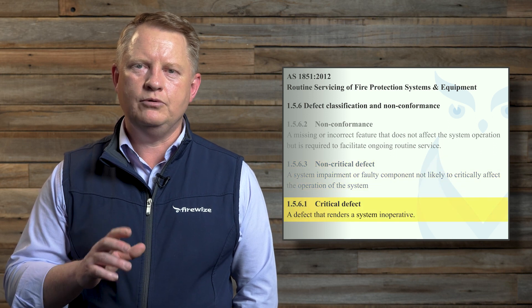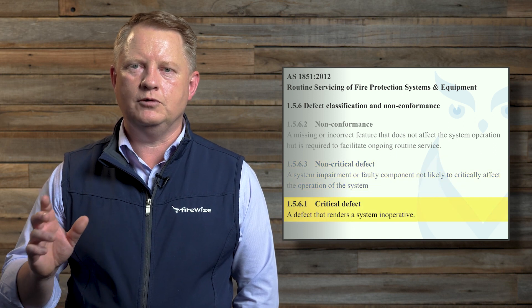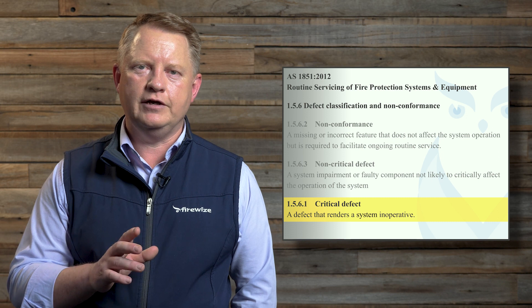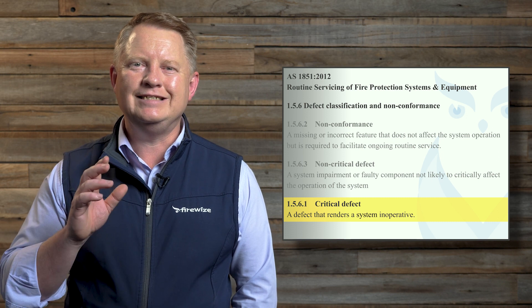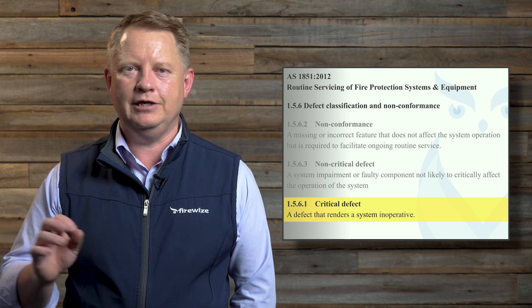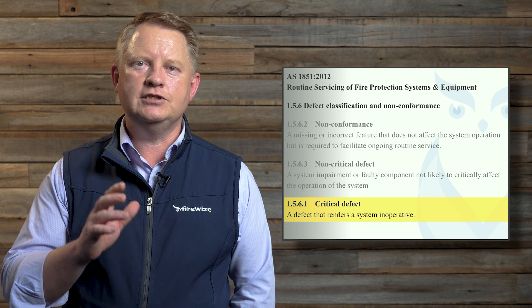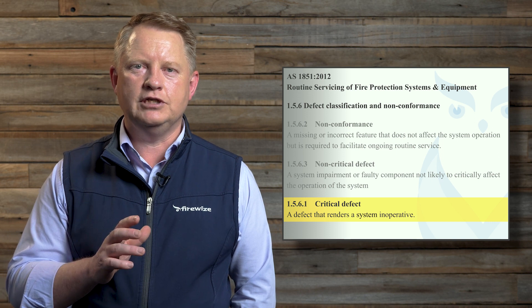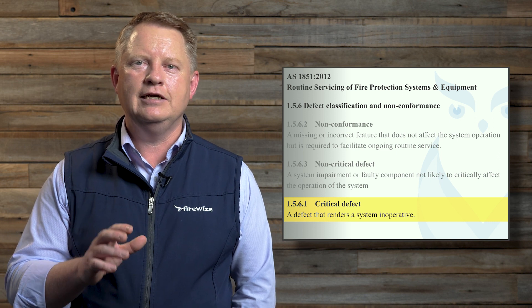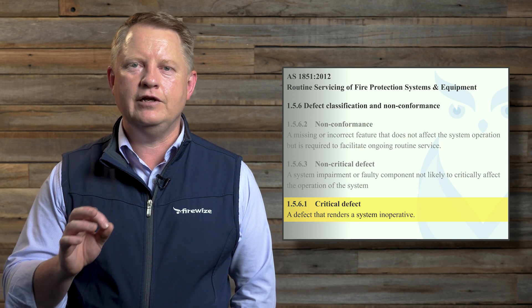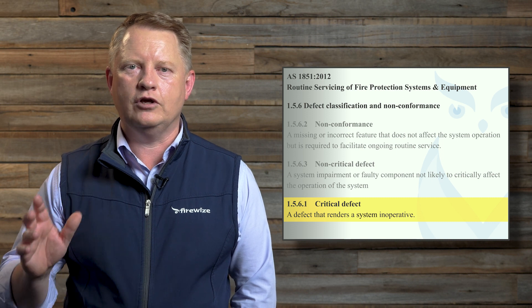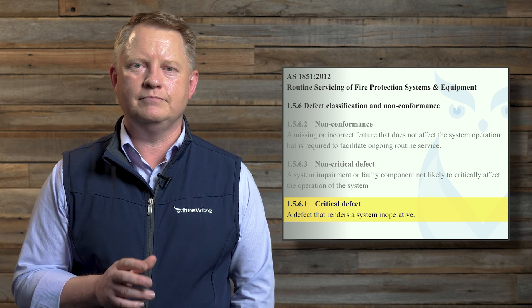And lastly, Clause 1.5.6.1 defines a critical defect as a defect that renders a system inoperative. A critical defect is reasonably likely to have a significant impact on the safety of the occupants of the building. There are examples of these defects in the standard and we'll go through a few with some pictures later in this video.